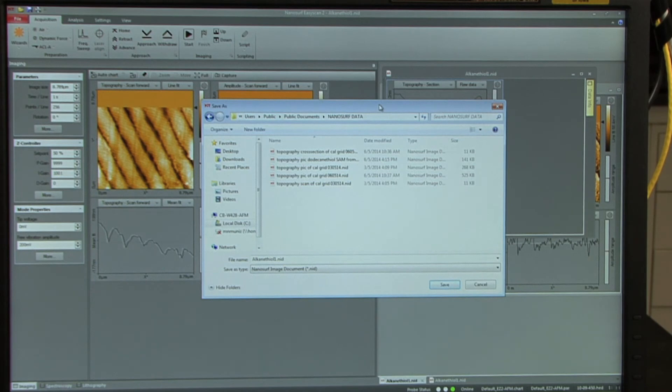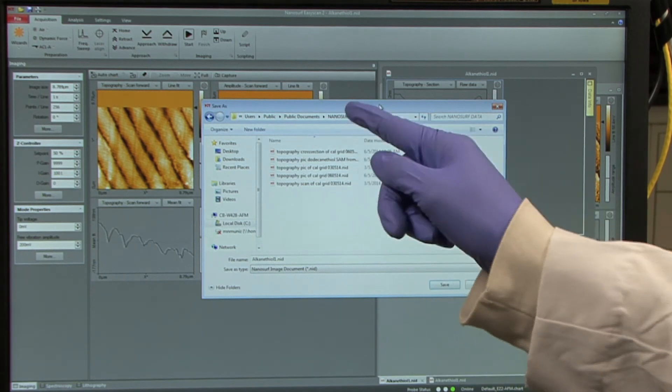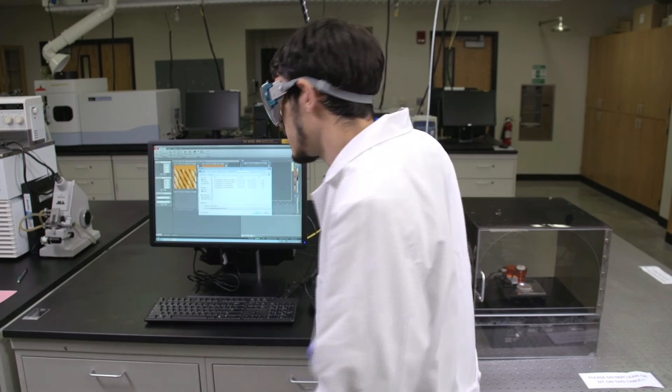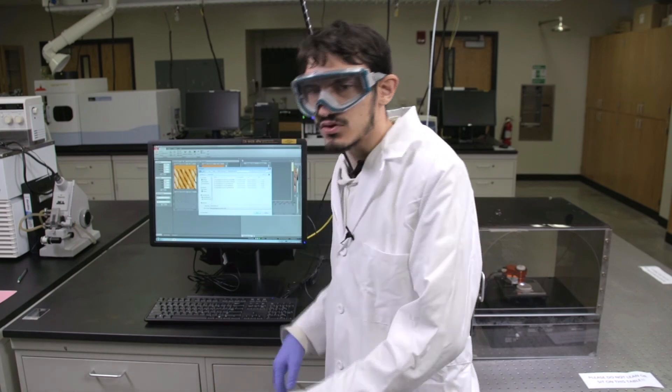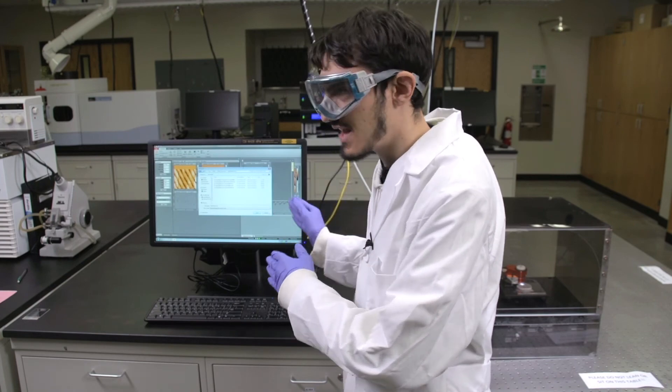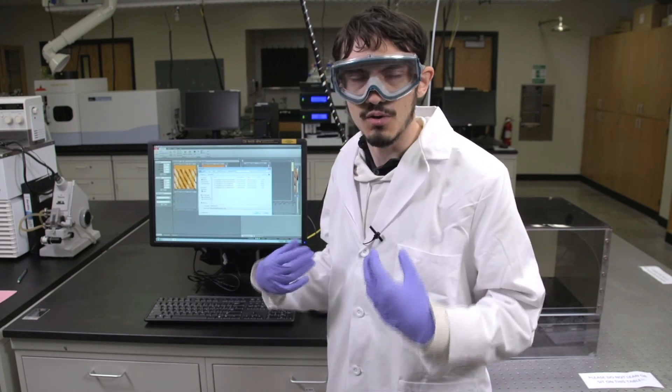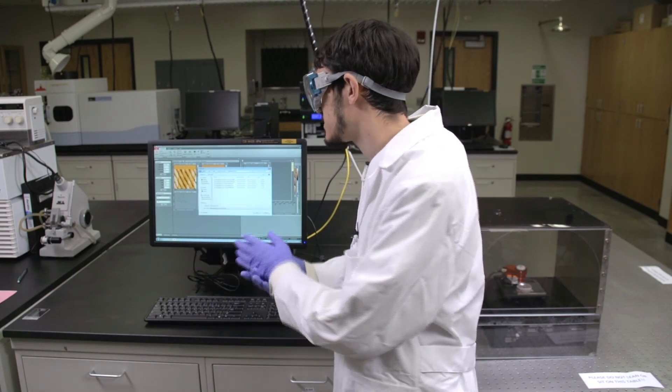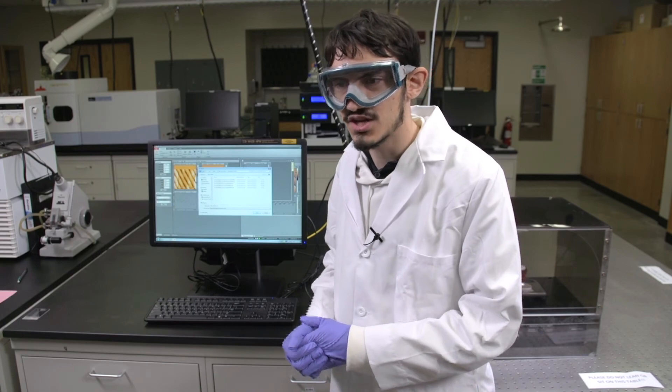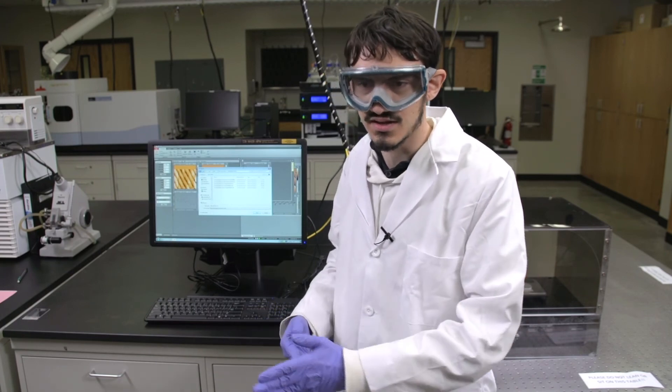You want to be sure to save all of your data in users, public, public documents, NanoSurf data. And then only after the instrument has been shut down and the software has been exited out of, you can go back in and copy and paste those files into your individual H drive. And make sure each team member logs in and does this.